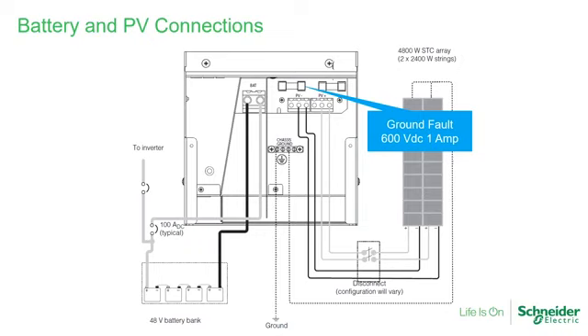In 99% of installations, the fuse is going to go on the negative side. The exceptions are a telecom installation, or a very specific requirement from the module manufacturer that says the array must be positively grounded; then the fuse would be on the positive side. Your typical installation, 99% of today's arrays, has the fuse on the negative side. If you have multiple charge controllers, each one will have the fuse installed in the negative conductor. Per NEC code, we're bonding the ground and the negative right here on this fuse holder. You don't have to do anything. This is already within the circuit of the MPPT80. So once you put the fuse in there, now you have a bonding.